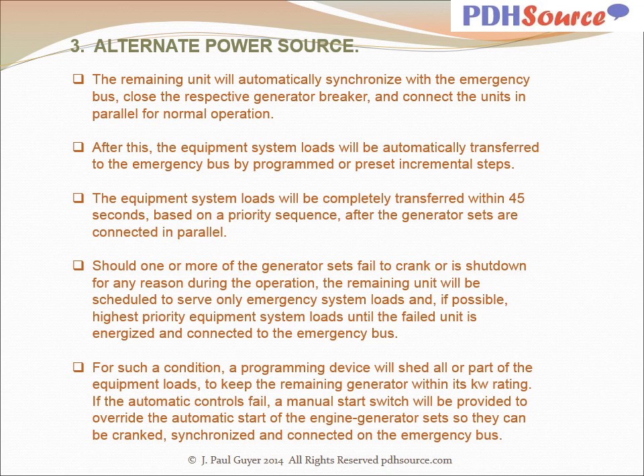The remaining unit will automatically synchronize with the emergency bus, close the respective generator breaker, and connect the units in parallel for normal operation. After this, the equipment system loads will be automatically transferred to the emergency bus by programmed or preset incremental steps. The equipment system loads will be completely transferred within 45 seconds based on a priority sequence after the generator sets are connected in parallel.